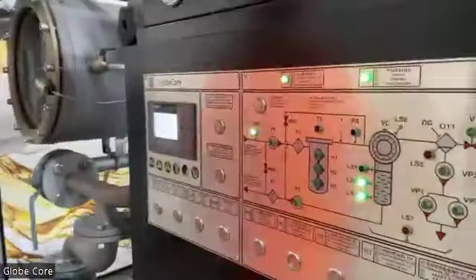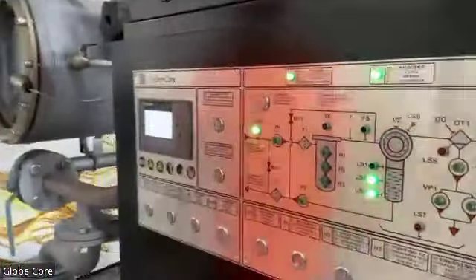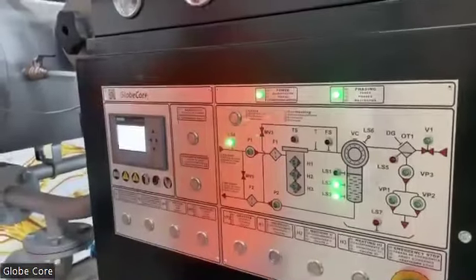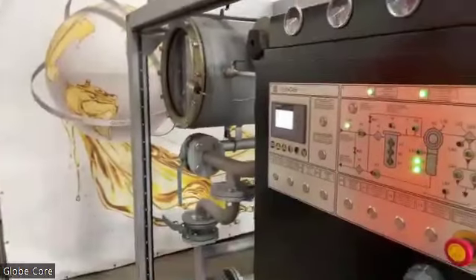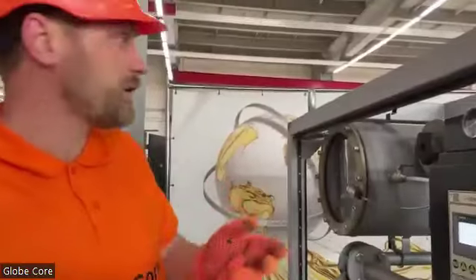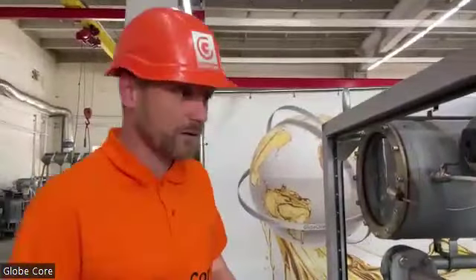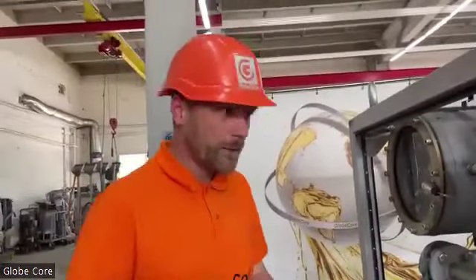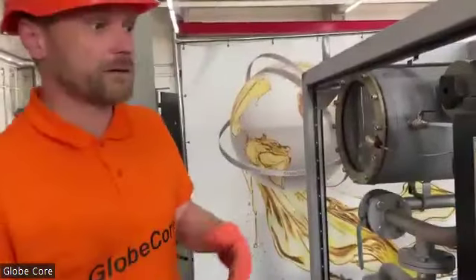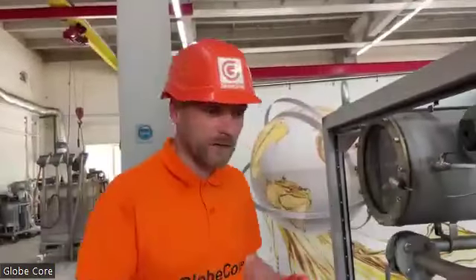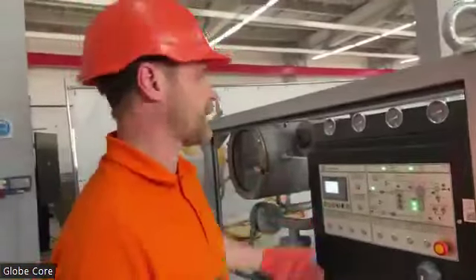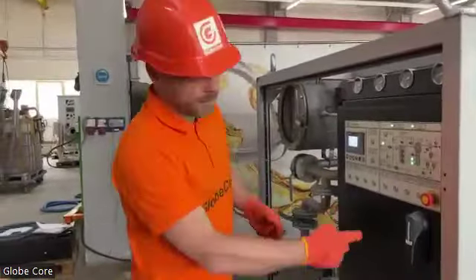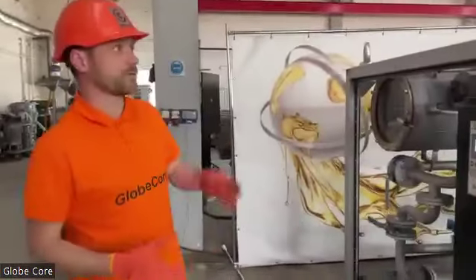The internal circulation lasts until we raise the temperature inside the unit up to the set value. Normally it is 55 centigrades. And pressure inside the vacuum chamber should be lower than 2 millibars. So internal circulation is supposed to be finished when we reach this temperature and this pressure. While this process runs, we prepare the first portion of oil. If we get these parameters, I mean temperature and pressure, we can start treatment of oil from the external tank. So we can open the inlet valve, start the inlet pump to let oil in, and open the outlet valve to let oil out. After internal circulation, we can treat oil from external tanks.